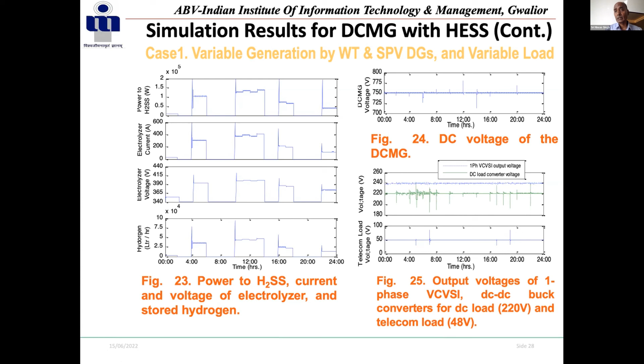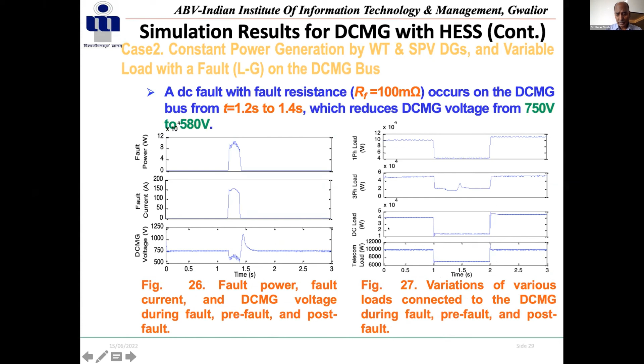So these are various cases, including when a fault is present, because we tested not only normal conditions and changes in load and generation variations, but also single phase and three phase faults, to see how the control algorithm responds. This was tested as a line-to-ground fault for 0.2 seconds, and you can see our system completely takes care of the load, telecoms, etc.